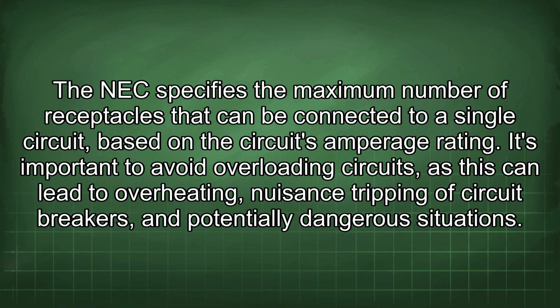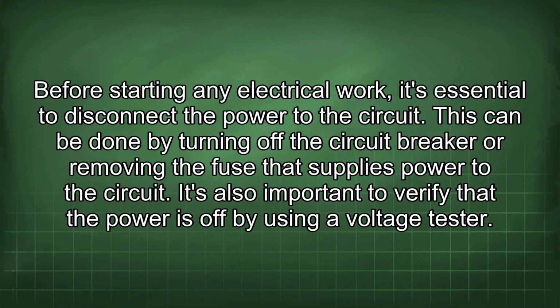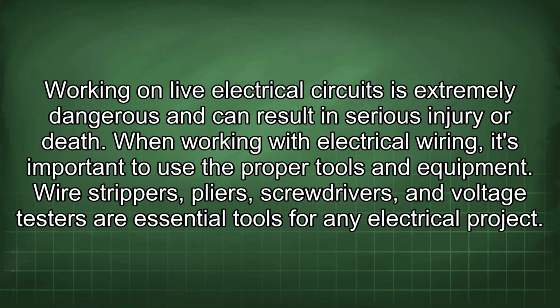potentially dangerous situations. Before starting any electrical work, it's essential to disconnect the power to the circuit. This can be done by turning off the circuit breaker or removing the fuse that supplies power to the circuit. It's also important to verify that the power is off by using a voltage tester. Working on live electrical circuits is extremely dangerous and can result in serious injury or death.